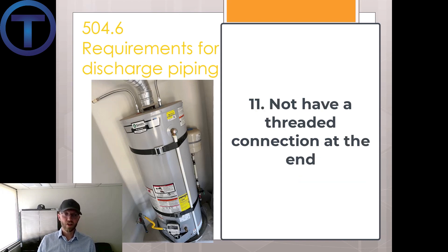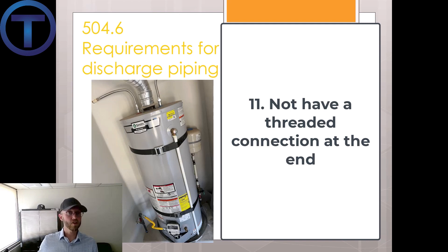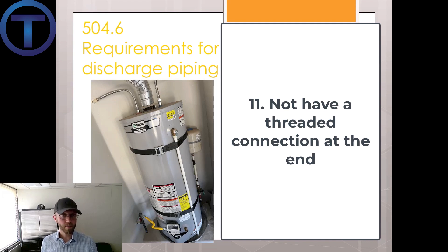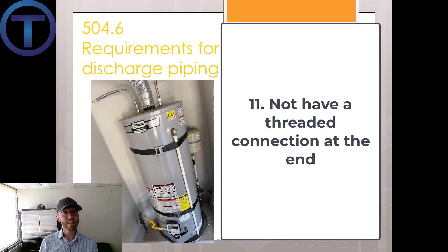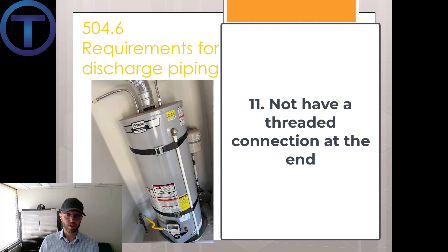Number eleven: shall not have a threaded connection on the end of such piping. They used to make these discharge pipes out of galvanized pipe — just grab a scrap, thread it, and throw it on there. If there are threads on the bottom and someone notices it's leaking, they might put a cap on there. That significantly increases the danger because now there's no place to relieve the excess pressure.